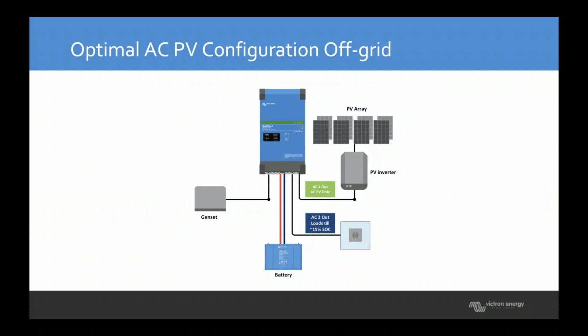So on the Victron Multi Plus, there's 2 AC outputs to the system. The first AC output can be considered the essential one, the reliable one. It's always connected when the Multi Plus is on and operating. But there's a second AC output, AC out 2. And that AC out 2 has an internal switching relay inside. So it can be connected or disconnected. And you can program that depending on certain parameters. Out of the box, it only works when the AC input is connected. So if you've got a generator running, you'd have a very large load, let's say a hot water supply or an air conditioning system or something like that, connected to the AC out 2. So that only runs when you've got the support of AC input.